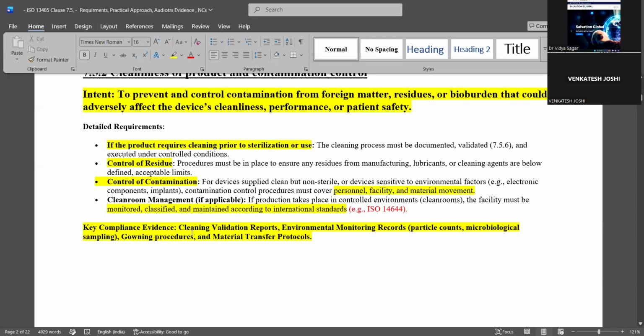Okay, you can clean with ethanol or some hydrogen peroxide, but you should see that whatever cleaning agent you are using should not affect the product. Either you can just clean if there is any particulate matter, using a vacuum pump or high pressure air. If there are microorganisms, you can clean them with spirit or ethanol or with hydrogen peroxide so that the bioburden or microorganisms come down. When they come down, the endotoxin levels also will come down because the microorganisms have come down. So the sterilization becomes easy.